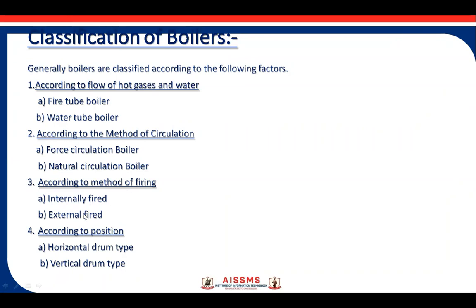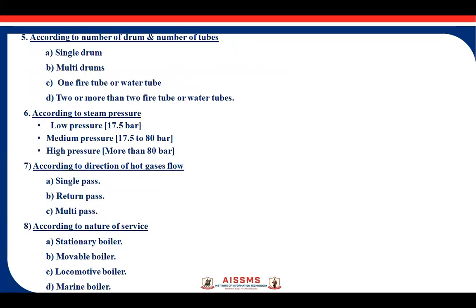According to the method of firing, there are internally fired and externally fired boilers — combustion or hot flue gases can flow inside or external to the tube. According to the position of the tube, there are horizontal tube boilers, vertical boilers, and in special cases some boiler drums or tubes are inclined to take advantage of gravity and for circulation purposes.